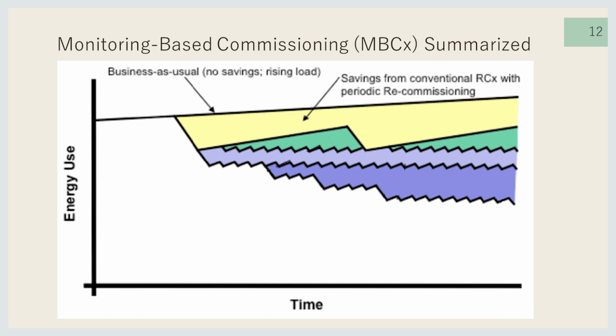The combination of the two is important because once retrocommissioning projects are performed, they sometimes remain vulnerable to drift or human error, or something at the site that disables what you just enabled. In some cases, because retrocommissioning projects are controls intensive rather than hardware intensive, involving sequences of operations, settings, and set points, they remain vulnerable to being changed accidentally or deliberately, such as during a test that isn't shifted out of manual mode.